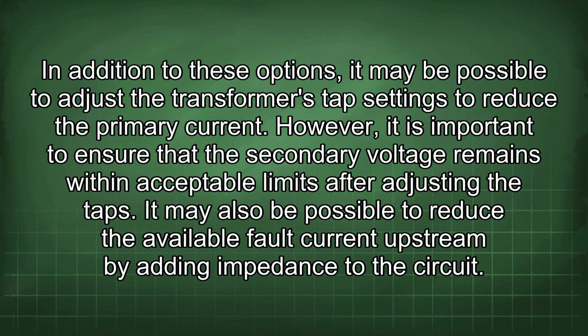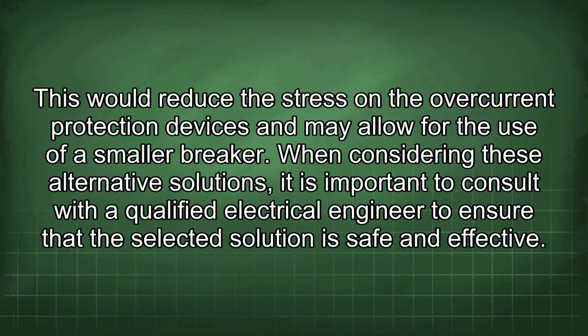In addition to these options, it may be possible to adjust the transformer's tap settings to reduce the primary current. However, it is important to ensure that the secondary voltage remains within acceptable limits after adjusting the taps. It may also be possible to reduce the available fault current upstream by adding impedance to the circuit. This would reduce the stress on the overcurrent protection devices and may allow for the use of a smaller breaker.